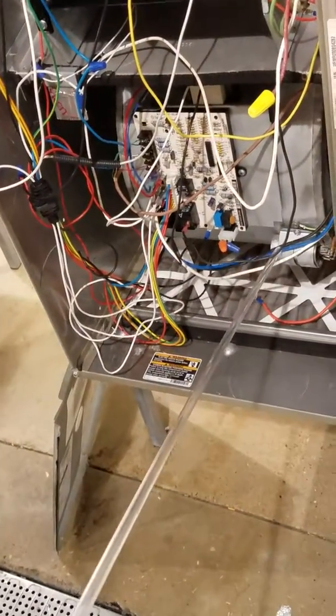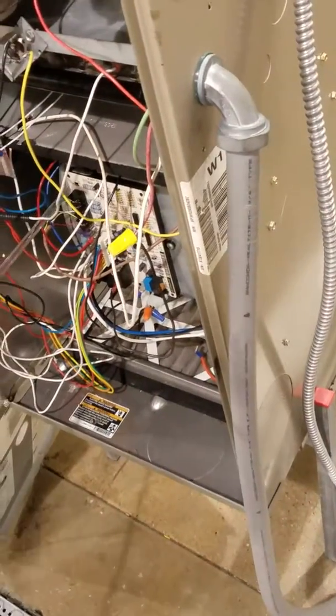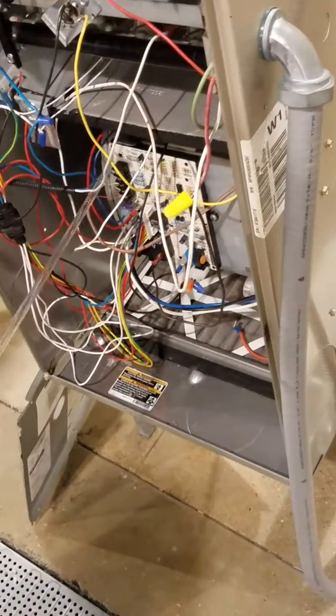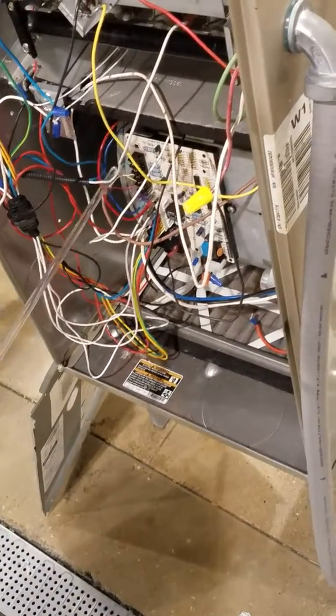All right. So I got my capacitor, I got my circuit board. Now I'm getting back to my low voltage, my G, which is for the blower fan motor, goes on G. Then I got white, W rather. W is the initial for white, which is heat, that will go on W. And then I got Y, like a yang, which is the initial for yellow, and that will go on my yellow terminal, which is for cooling. And then I got the red, which will go on R. R is the initial for red. There's a power, and finally I got blue. That will go on C.